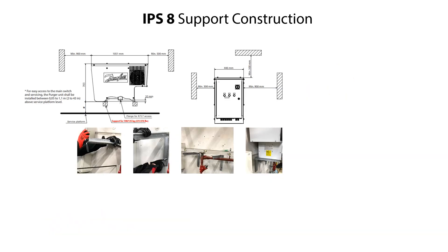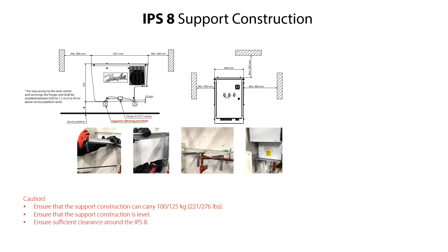When installing the IPS-8, it is very important to ensure that it can be mounted on a support construction as shown and specified here. The support construction should be able to carry 100 kg or 221 lbs, and for the IPS-8 UL version, 125 kg or 276 lbs. The support construction should be leveled and there should be sufficient clearance around the IPS-8 for easy service access and sufficient fan cooling.